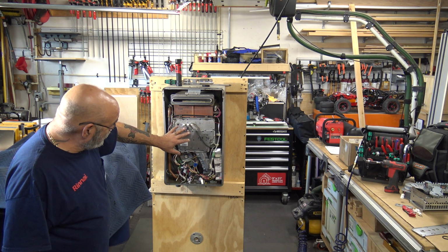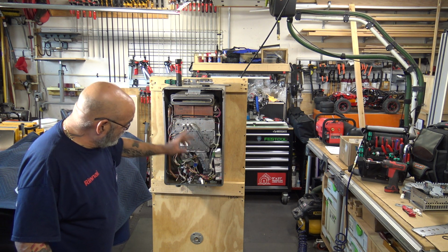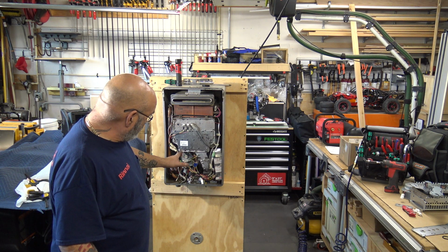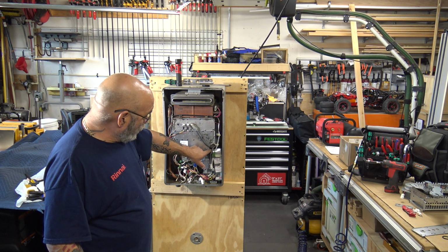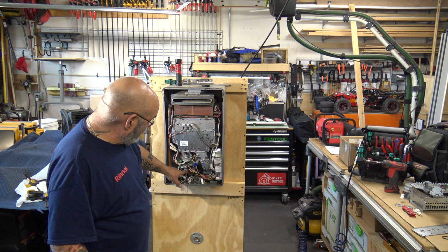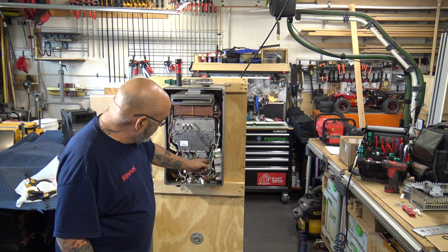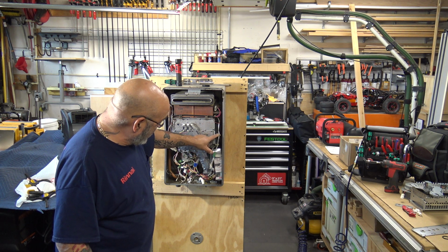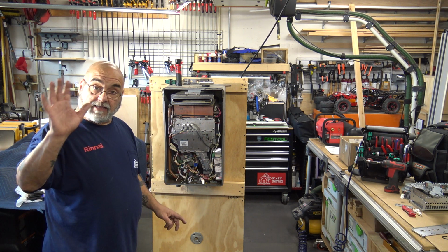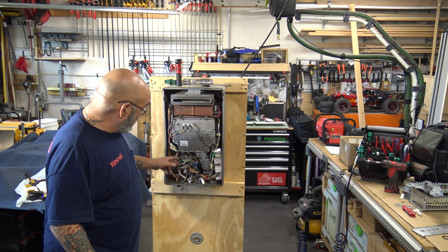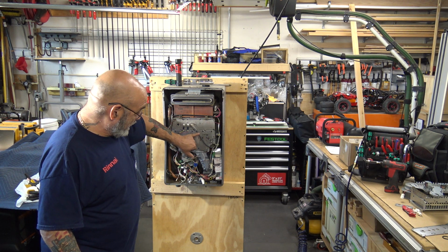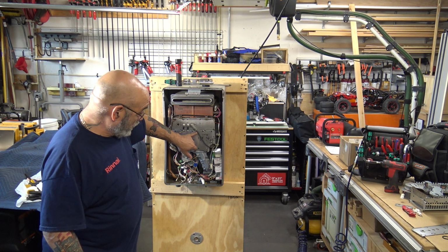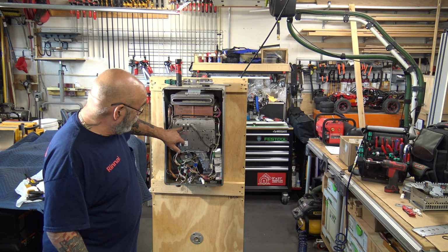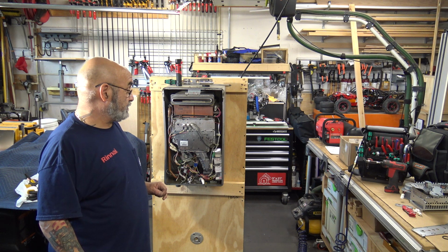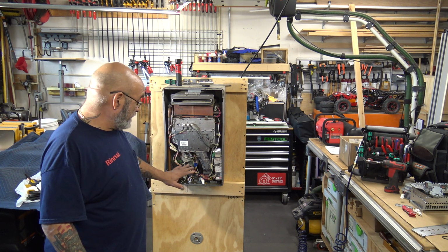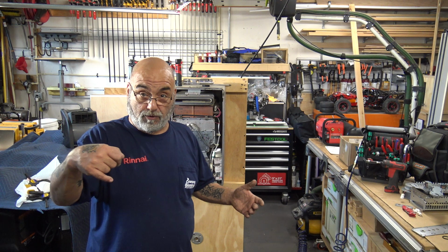Just double check, make sure everything is pushed in. Make sure that you have the 1, 2, 3, 4 solenoids. You have the fan plug, and you have these 2 gray wires from the igniter. So remember those were the wires: igniter, fan, and 4 solenoids, and then this is part of the igniter, of course, and then your 2 flame sensors. That's the whole thing that you should be unplugging, of course, or the unit.